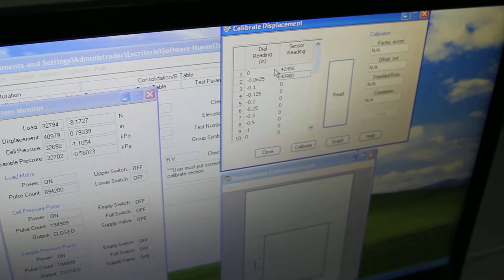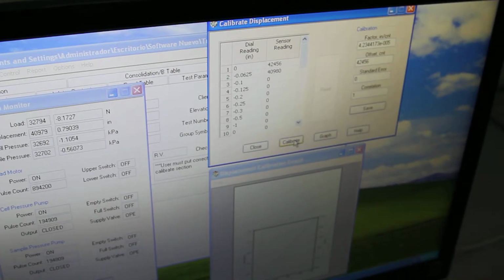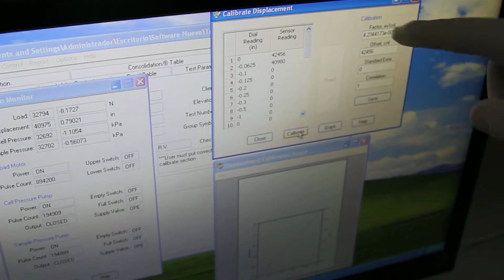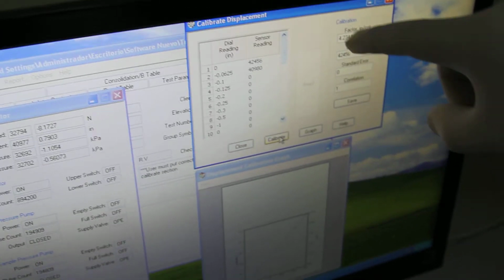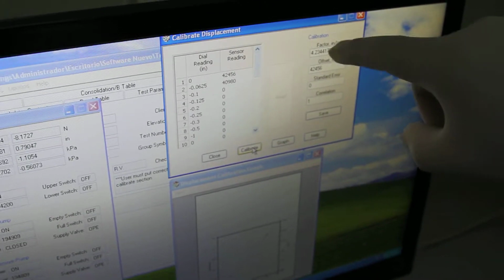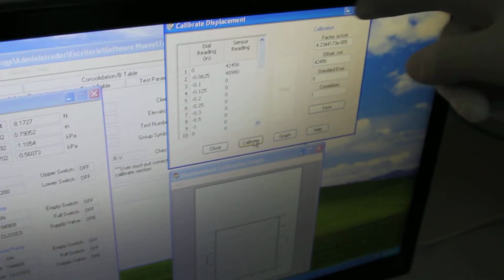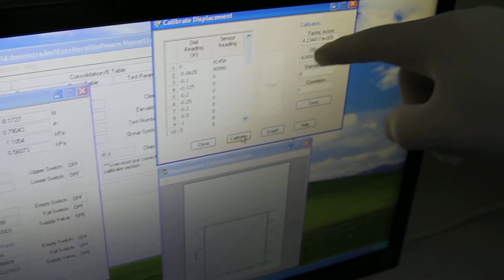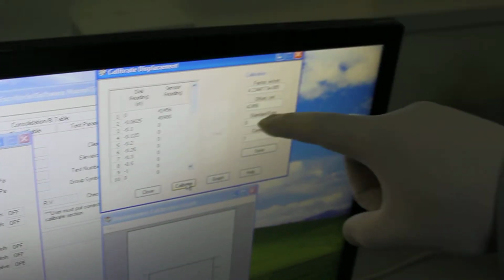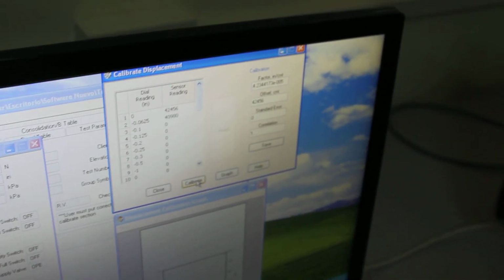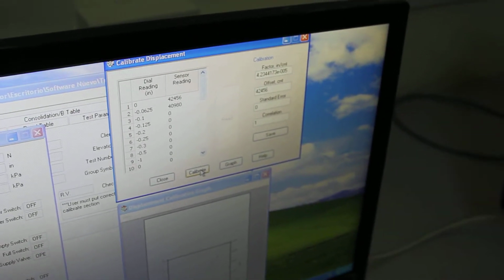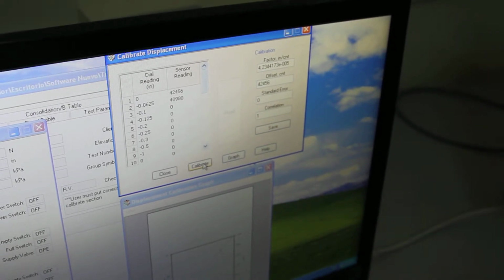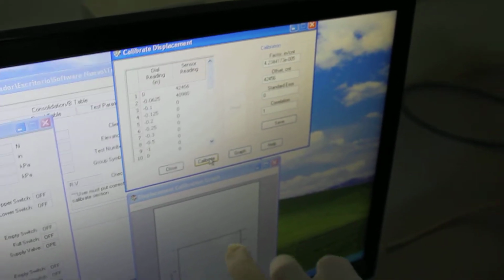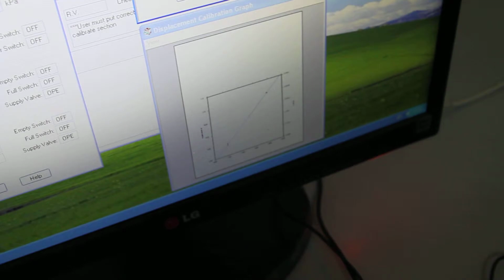So I have 2 points now. I can do calibrate. Based on 2 points, the software automatically gives you the factor in inches or millimeters per count. There's an offset, which is a theoretical offset, a standard error, which is 0 here, and a correlation of 1, because this is a perfect line because of the 2 points that you see here.